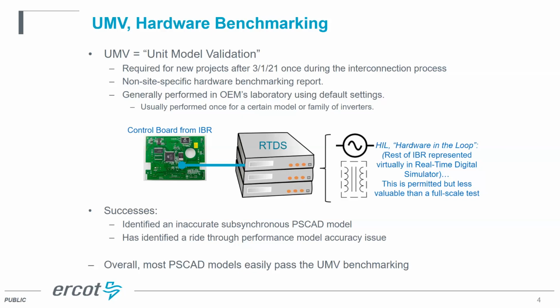This determines that the PSCAD model is structurally correct. It does not have to be site specific. They can use default parameters, and we don't currently require them to test the full scale machine. They can just test a stripped down machine, testing a control board and running the bulky components using hardware in the loop RTDS simulation.